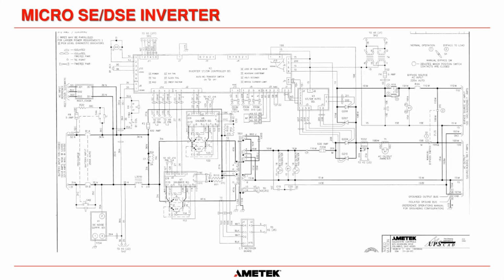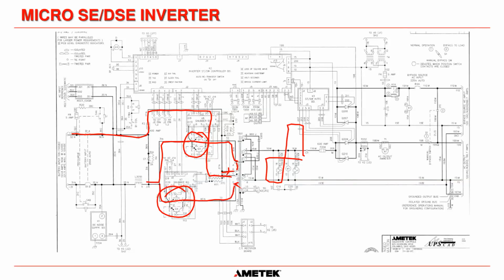But once again, I'll just go through here, through the fuse, down to this point here, we have positive at the center tap of the transformer. And then if we switch these IGBTs on, negative now goes to this side of the transformer, and you will get the negative going pulse there. And then we switch it round and turn these ones on. Negative goes that way to that side of the transformer, and that would give our positive. And we would do that 60 times a second.